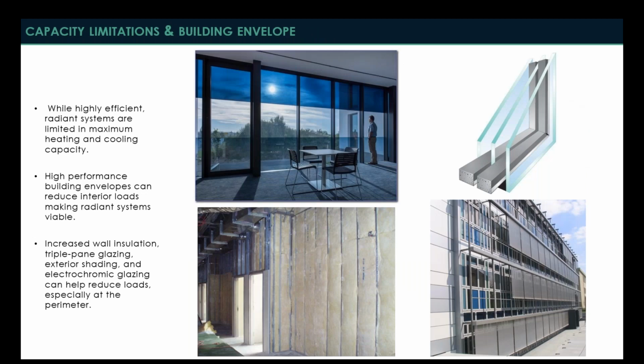Another thing that I mentioned earlier is the capacity limitations. These radiant systems do have limitations on capacity. In an all air system, you can always just pump in more air. That's not the best idea, but it does increase capacity. With radiant systems, there are limitations. And so the building envelope becomes extremely important in making the use of these systems feasible.